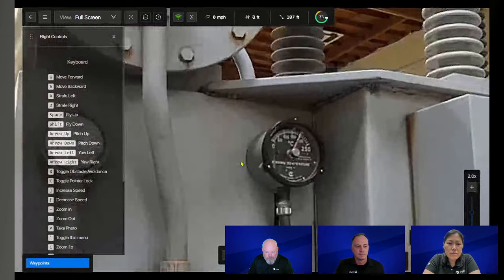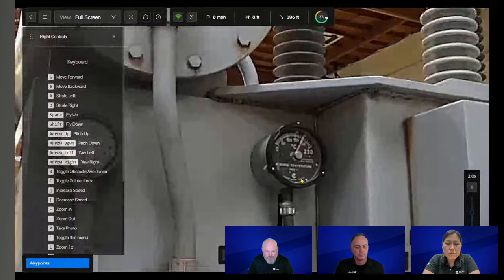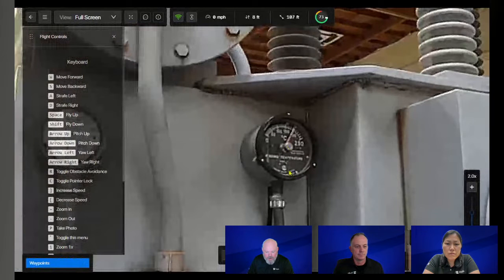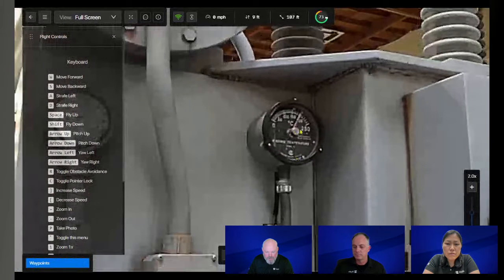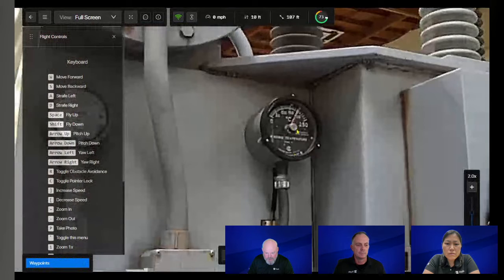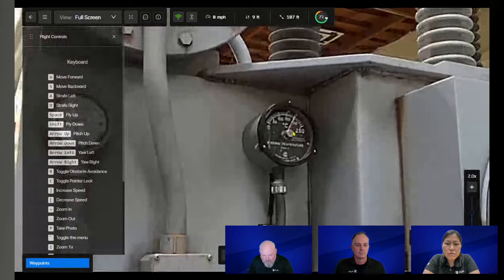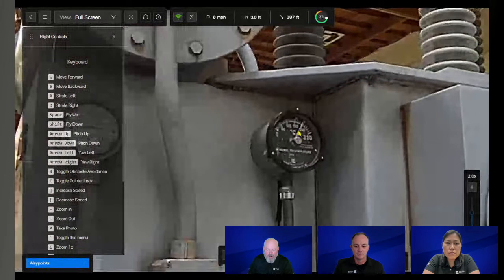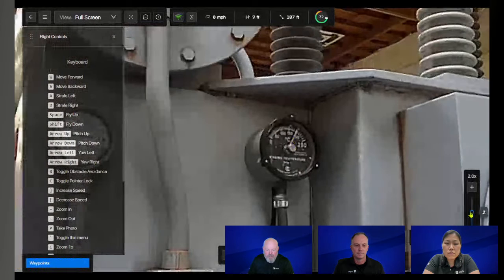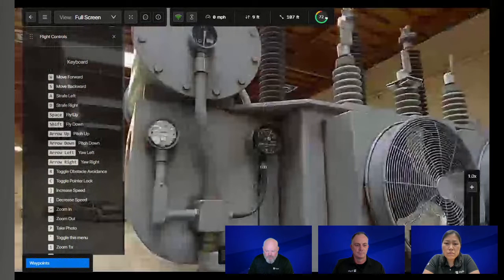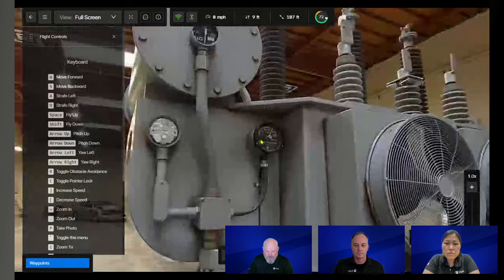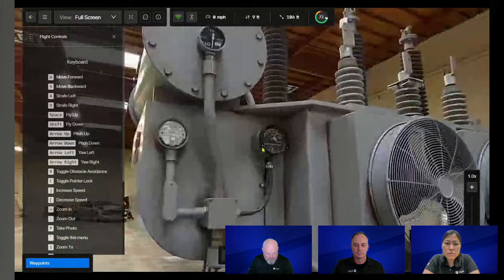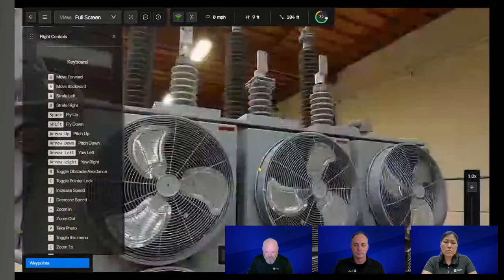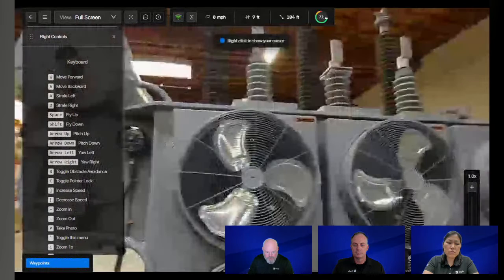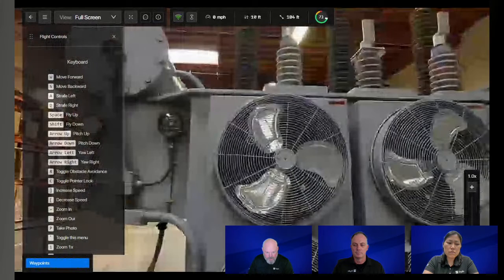Yeah, so I stopped here at our high side winding temperature gauge, and I see that it's a little over 105 C, and it's on the contacts where all the fans should be running. So the fans should be running. We've got a low oil situation, and I feel like we might need to send somebody out and have them put their hands on the station and see if they can fix it.